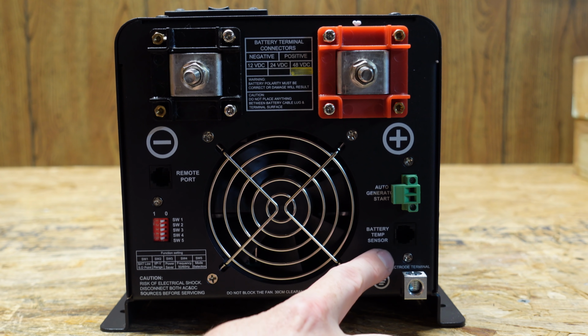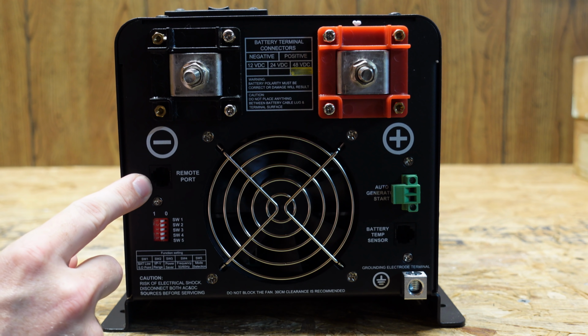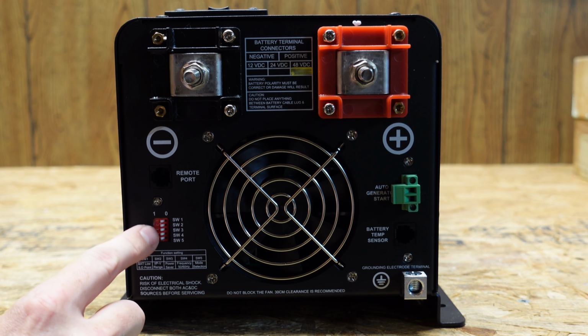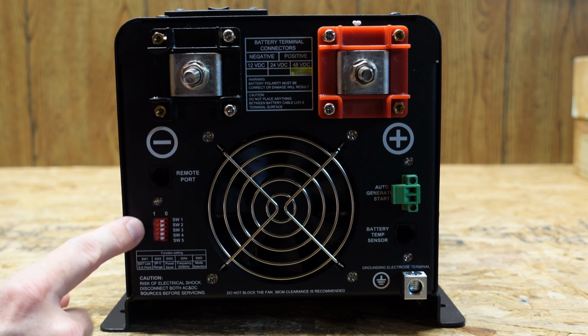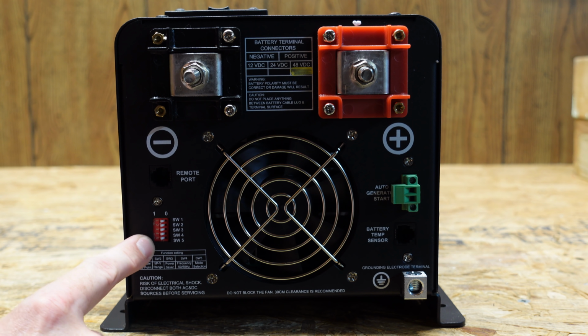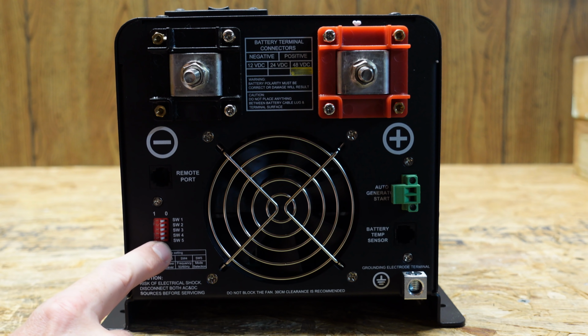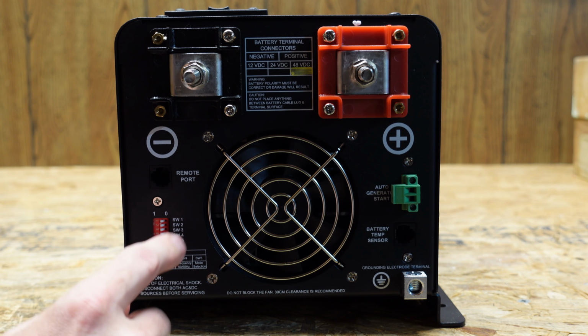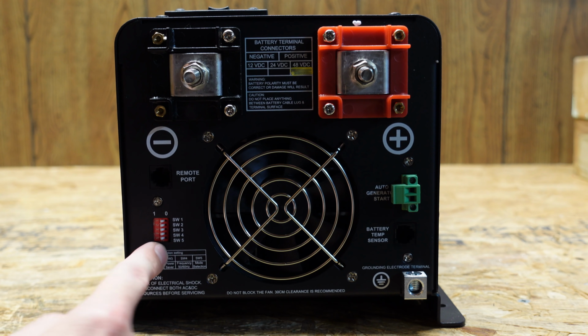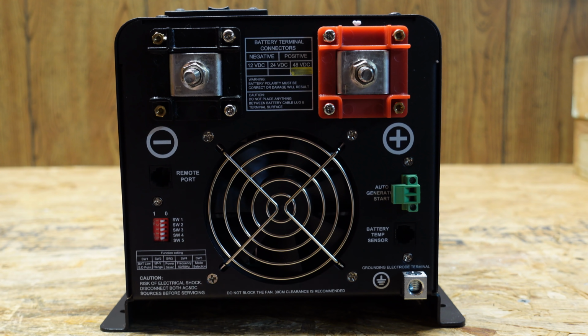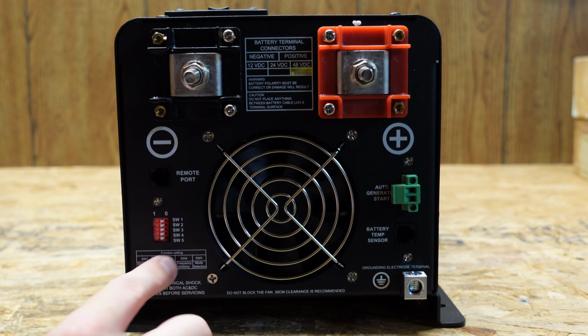We have a plug for a remote temperature sensor, a plug for a remote control panel, and a series of DIP switches so you can set things like your low battery trip point, AC input range, operating frequency, and priority mode. So if you want this to operate with utility having priority, acting as a standby UPS, or you can have this running in battery priority, such as if you're off-grid.